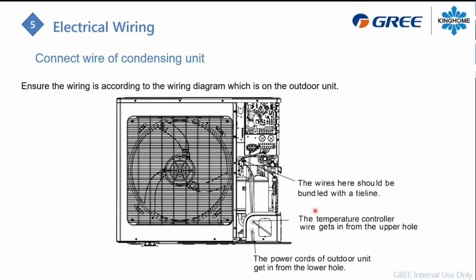Make sure when you get the wire across the corner panel to use the proper hole. So one hole for your high voltage line and another hole for your low voltage line. Make sure you're not passing from the same hole. You have access from the side, you have access in the front, and you can have access from the back too. So multiple ways to install your wire to make sure you have a proper connection from your L1, L2 right here, and your low voltage connection just beside it.